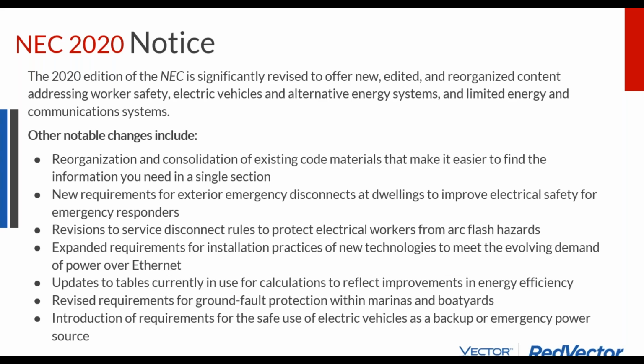Also, there was a safety issue because you're taking the power system of the building outside in a readily accessible location. Someone got into that box, they could stick their hand in and electrocute themselves. And that's really a solar installer issue. These exterior disconnect switches need to be locked so that people can't open them up and take a look inside. But this is for fire safety. This is for the firemen to be able to come out on site, turn that switch, and de-energize the building.